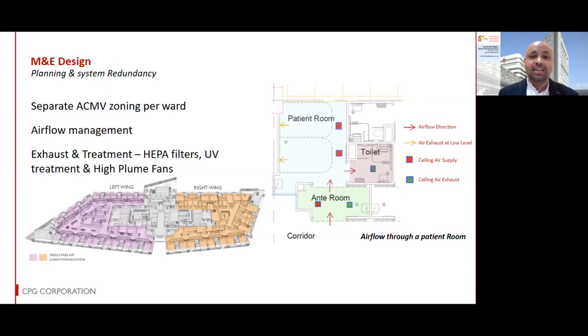One of the key design considerations for M&E, for pandemic-ready facilities, is the airflow management within various spaces. The idea is to keep a unidirectional flow of air from clean areas to dirty areas. In times of outbreak, the patient areas are considered dirty, and the staff needs to be protected by careful design of the airflow within the facility. Patient rooms can also be designed with negative pressure, single pass air conditioning. The exhaust air can be treated using HEPA filters and UV lights before discharge.